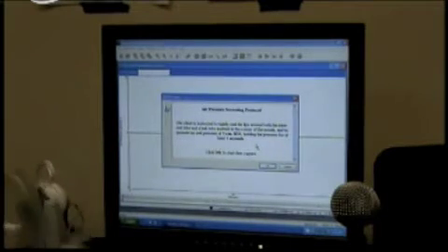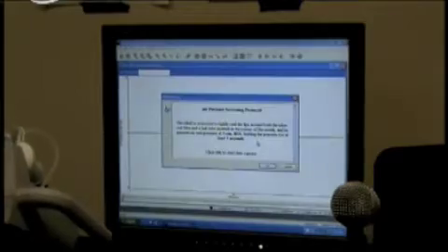Okay. So we can do a protocol for air pressure. We go to air pressure, new live input, and it'll change the screen. It says the client is instructed to tightly seal lips around both the intraoral tube and the leak tube inserted in the corner of the mouth, and then generate an oral pressure. It's the plastic thing that goes in the mouth. Holding the pressure for at least 5 seconds. Click OK to start capturing data. So you want them in place.